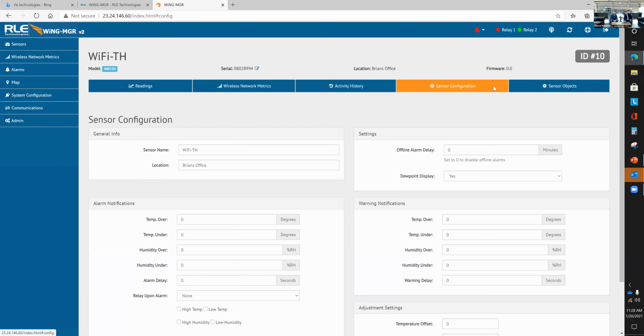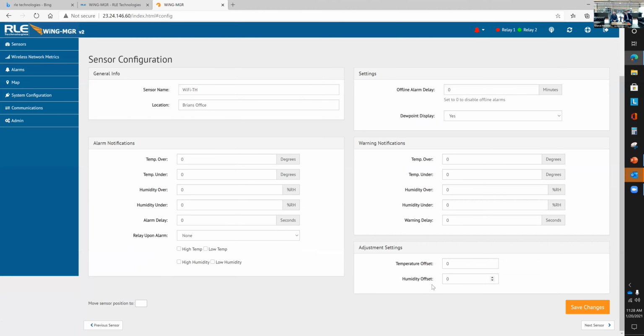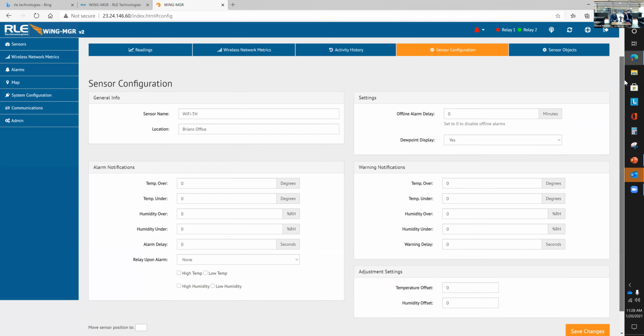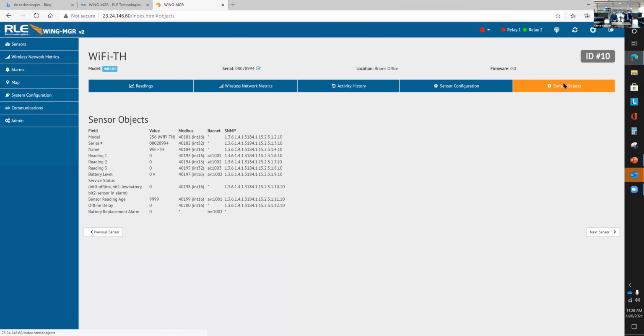Here you will see some of the other features of setup, and also an offline alarm delay you can set up. You can also auto-populate dew point. Naming a sensor is about as simple as you'd ever hope. And here on the bottom with our temp sensors, this is a new feature we also added - a temperature offset and a humidity offset. So when you go through commissioning, if it's 0.2 degrees off or something that you really want to make sure is right, that's a way to right-size that value.